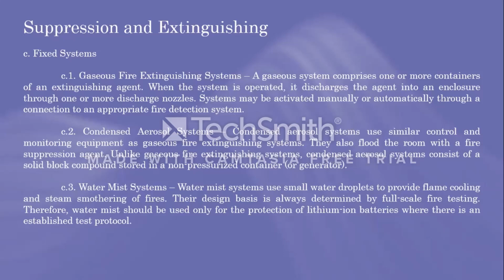The water mist systems use small water droplets to provide flame cooling and steam smothering of fires. The design's basis is always determined by full-scale fire testing. Therefore, water mist should be used for the protection of lithium-ion batteries only where there is an established test protocol. So these three here are the techniques or ways to extinguish a lithium-ion scenario, if there is a fire and if there are leaks. These are the systems.